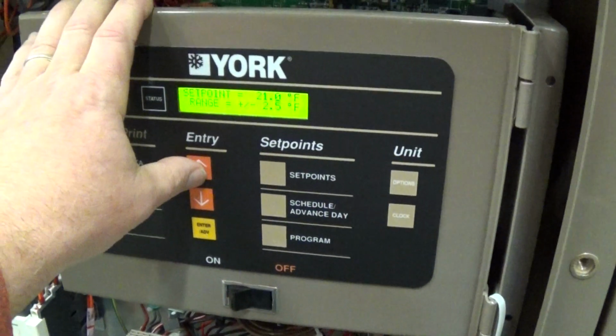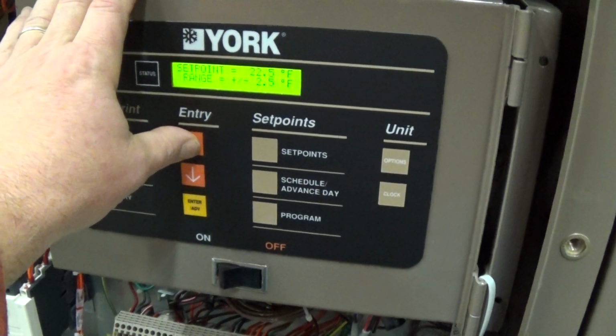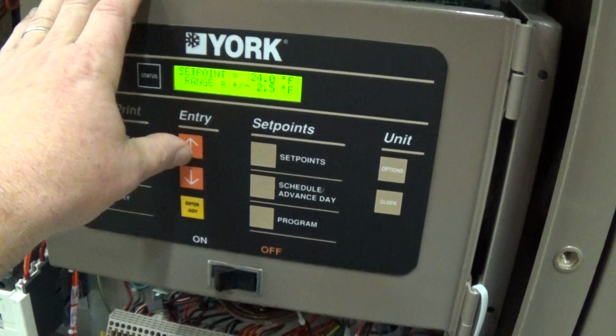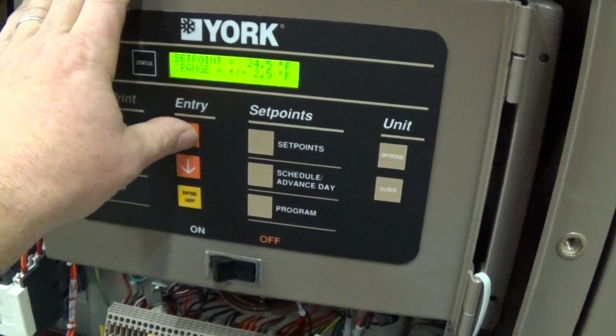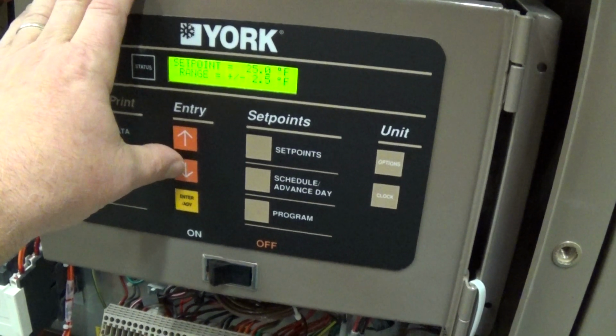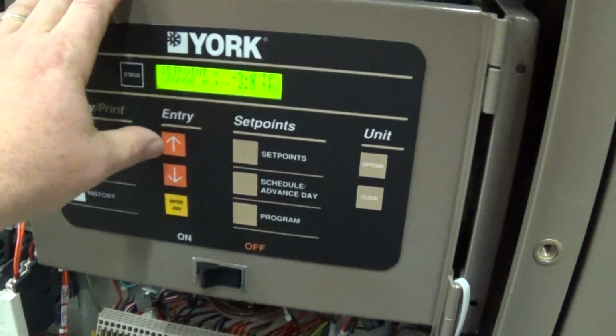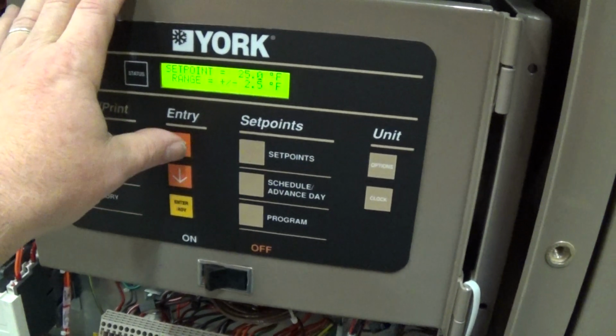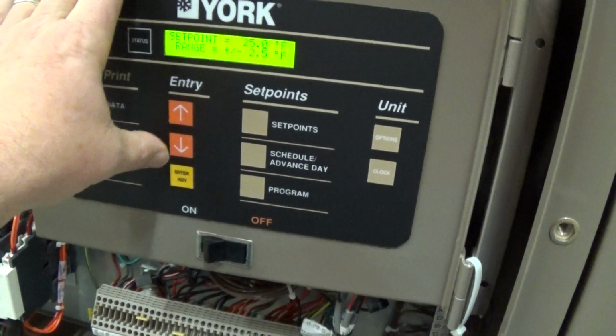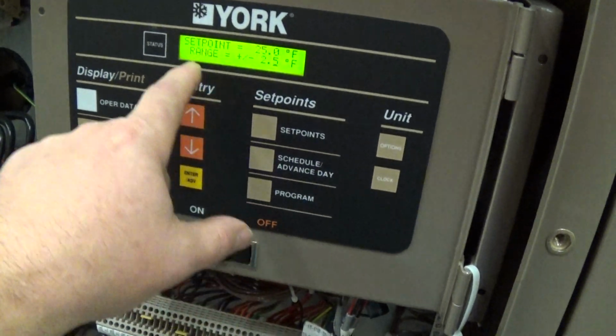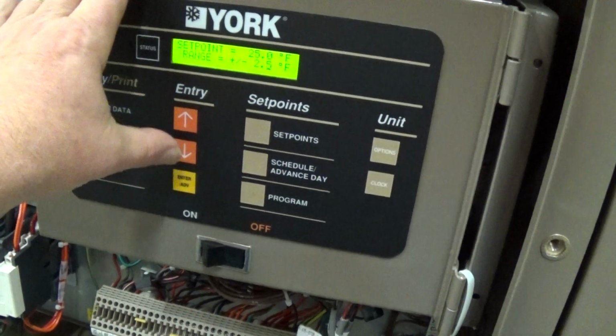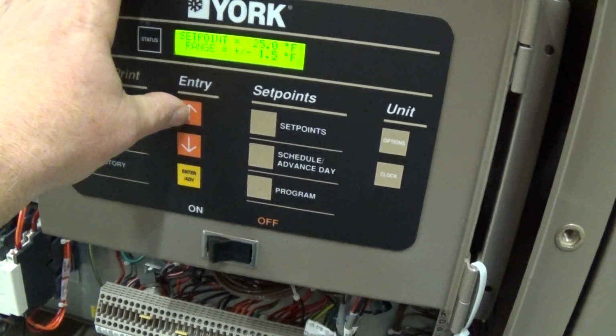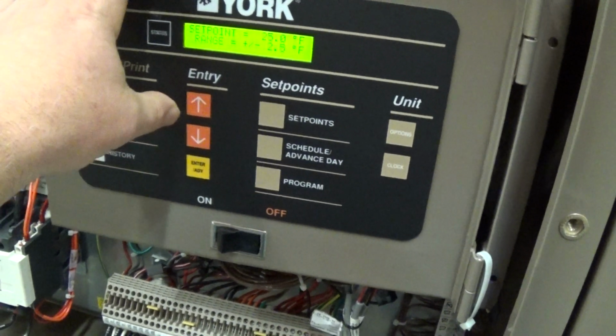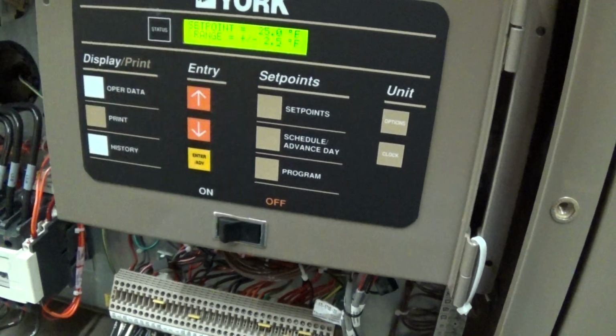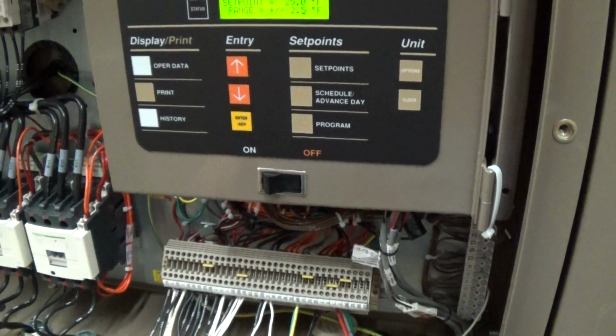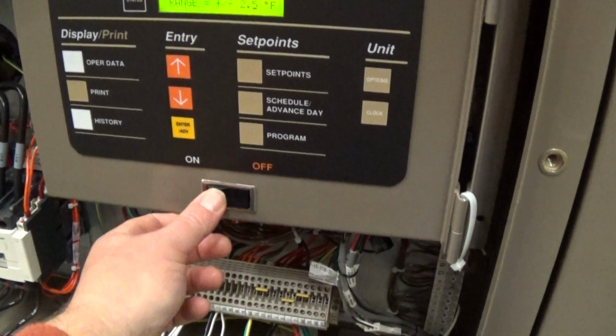For the customer that this is going to in Illinois, their application is going through a heat exchanger to cool some fresh water down to as close to freezing as possible. They're going to run at a 25F set point. So you can see after I press set points, you can just go up and down. Then when you press enter, it'll go down again to the range, and you have an option of plus or minus 2.5, 1.5, or 2. That's basically your differential.